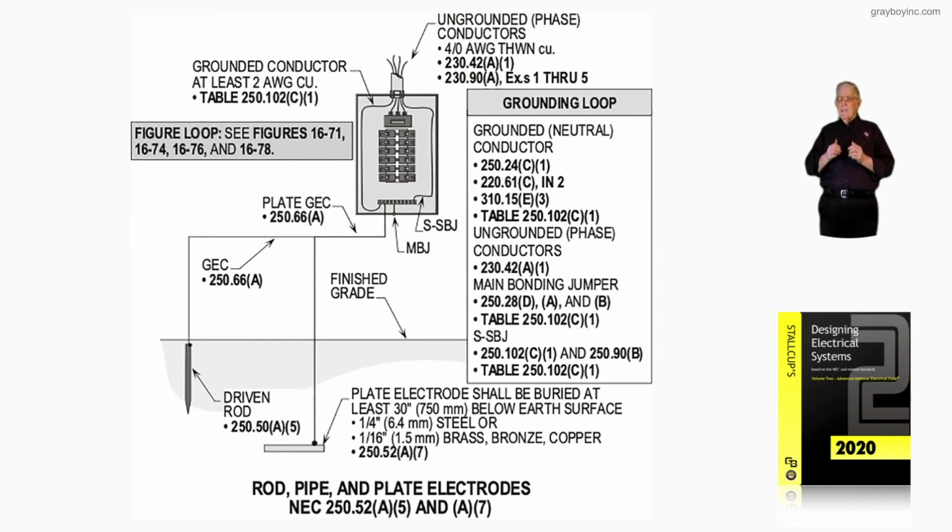So kind of keep that in mind. Everything would be number 2 in that panel board for grounding and bonding if the grounding electrode conductor connected to structural steel or a metal water pipe in accordance with 250.66 (A), (B), and (C).